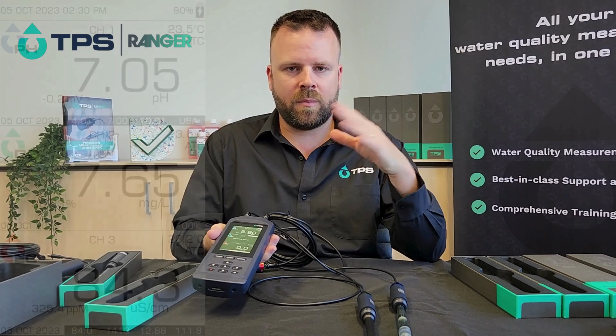I'm going to take off the ORP sensor and plug this one in, and you can see the screen automatically updates to show the dissolved oxygen reading. It takes a couple of seconds to initialize, but as you can see, it's a piece of cake to swap and change sensors as needed. You don't have to recalibrate them when you move between instruments — you can have them stored away and just plug them in as needed.